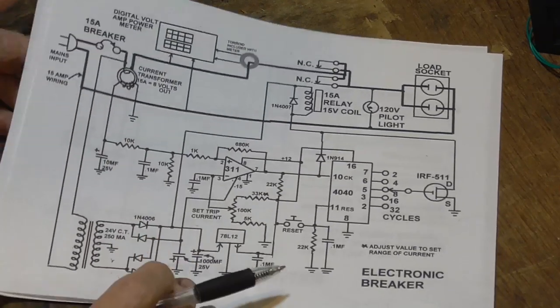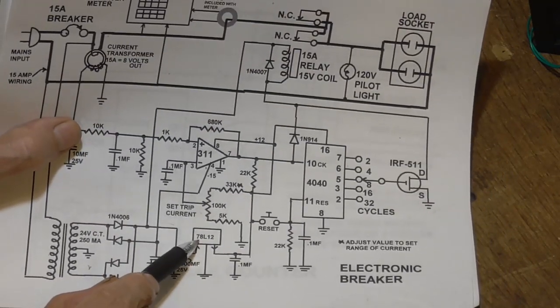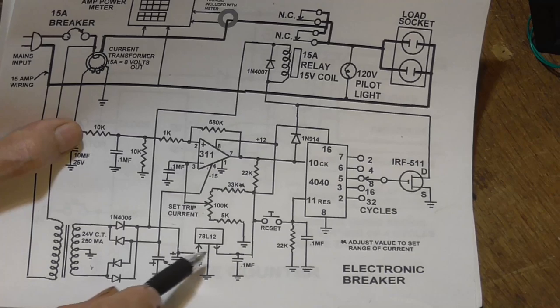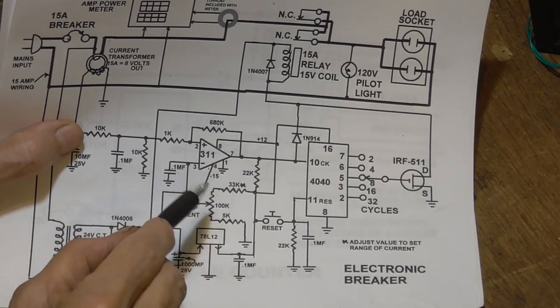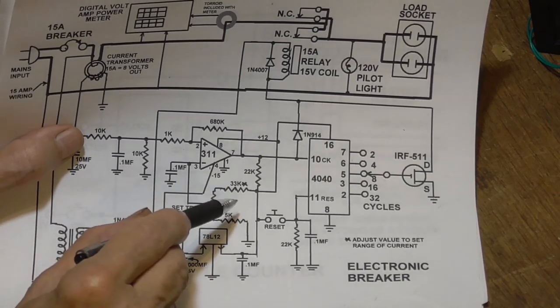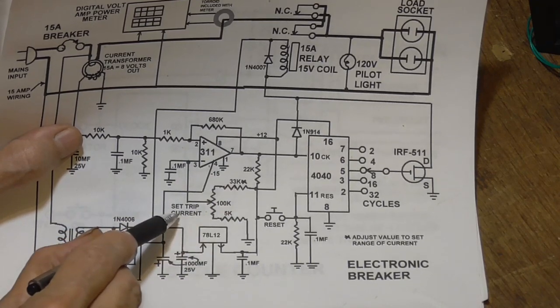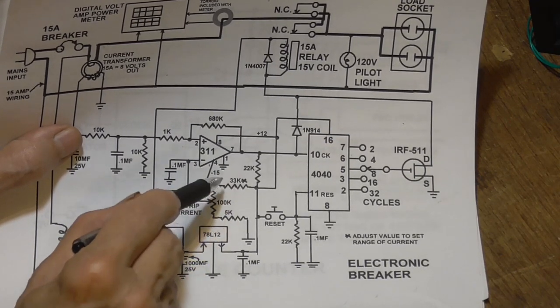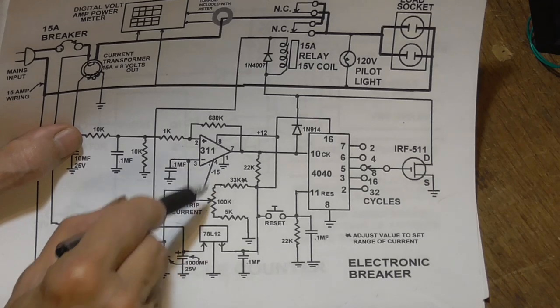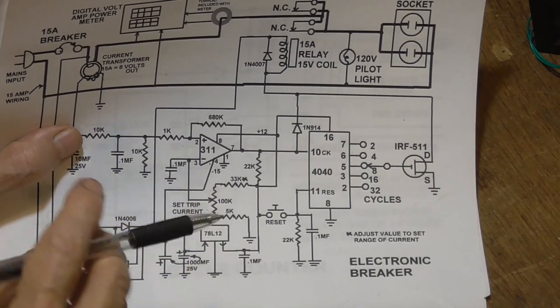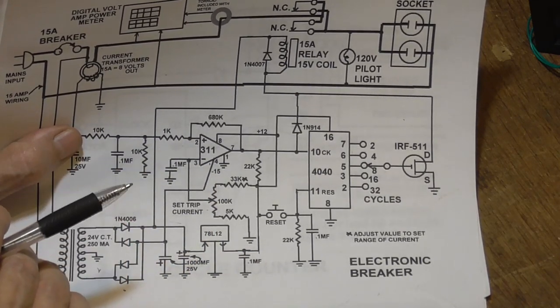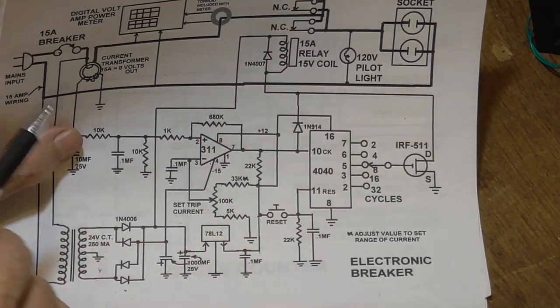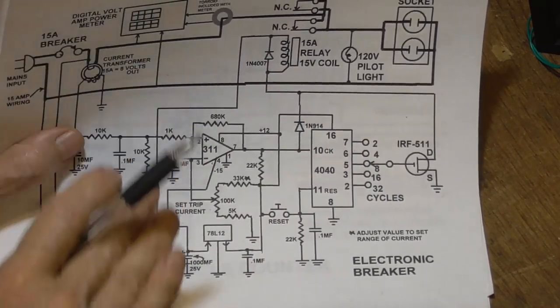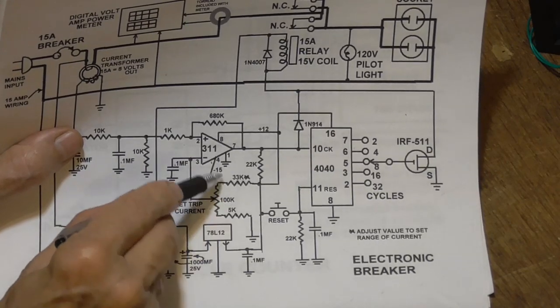That's the basic circuit. We have a 78L12 which gives us a regulated 12 volts for our set trip current, so that the voltage on our potentiometer doesn't vary. There could be a little variation in line voltage if we have a big load on this thing, and that could cause our trip point to change if we don't have a regulated voltage.